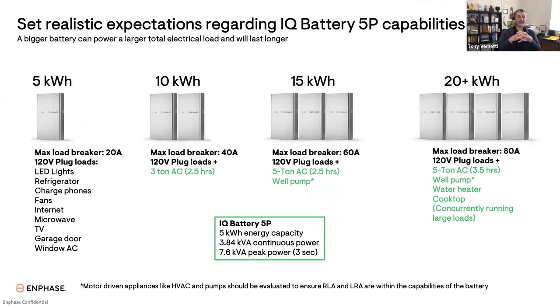And the same as you can see with SolarEdge Energy Bank. So one of the questions that needs to be answered during the initial design and sizing of the system is, what's the minimum size battery I need in order to run certain loads in my home? And you can determine that actually by looking at the breaker for that load. And I've got a few examples here to make this a little simpler.